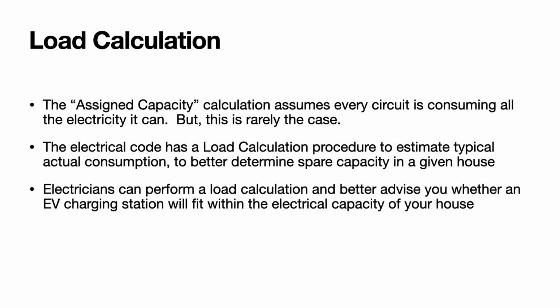Now, what electricians actually do is what they call a load calculation, and this load calculation procedure is defined in the electrical code. It takes into account, for instance, an estimate of the amount of lighting required to light the number of square feet in the house, and that turns into an electrical load to drive that lighting. Another thing it takes into account is the presence of a washing machine, dishwasher, refrigerator, and the typical usage profile of each of those devices. How likely are you to have the air conditioner going at full, plus the dishwasher, plus the clothes washer, plus the pool pump, plus all of that? How likely are you to have every single last thing running at the same time? That's unlikely. That's what the load calculation takes into account.